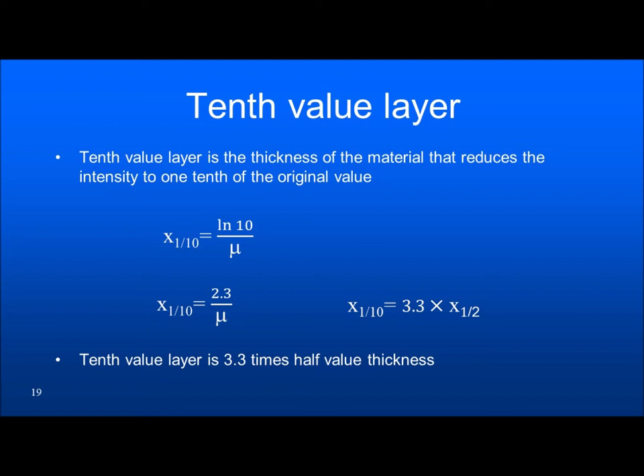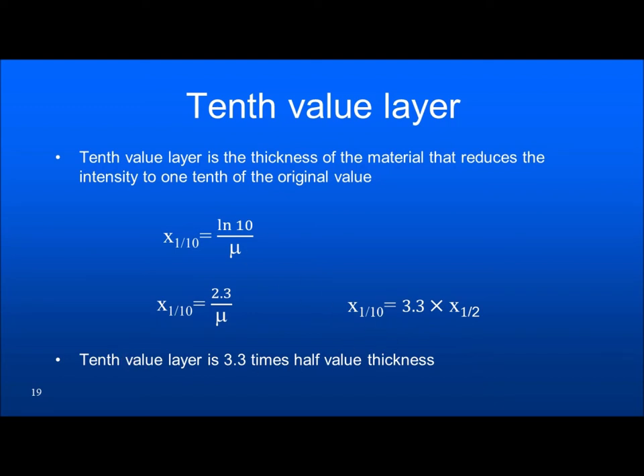The tenth value layer (TVL) is the thickness of material that reduces intensity to one tenth of the original value. It is also very important in radiation protection, particularly in shielding calculations. Tenth value layer = log(10)/μ = 2.3/μ. And there is a relationship: TVL = 3.3 × HVL. This is a very important relationship for shielding calculations.